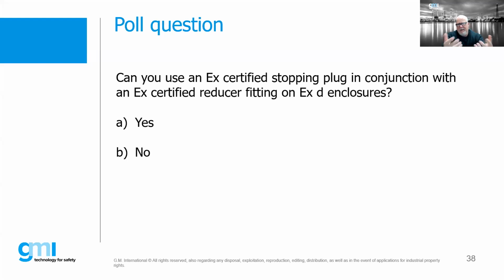We talk about this a lot in courses, and people ask why - what's the issue? I understand why people think, okay, I'm using a certified plug, a certified reducer, and I'm putting it in a flame-proof box, so we're still maintaining flame paths. But we're introducing an additional flame path in effect. The standard is very clear about this: it states we cannot use a reducer with a stopping plug. We can use a reducer with a gland, but we cannot reduce and then use a plug. We just need to use a single reducer, a single gland, or a certified stopping plug. It makes sense, because the flame path is part of your safety. Absolutely, absolutely.